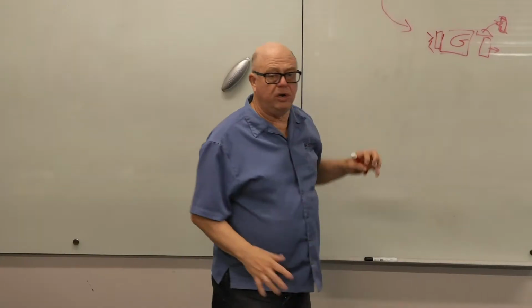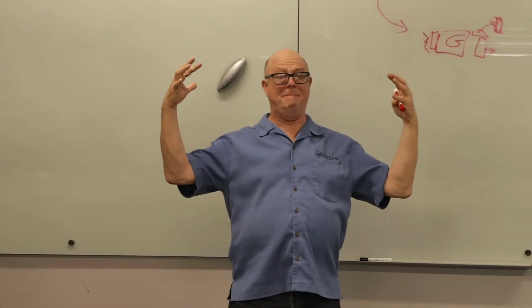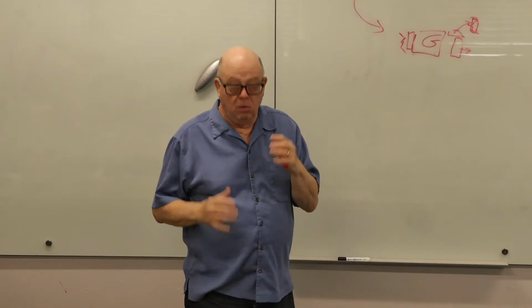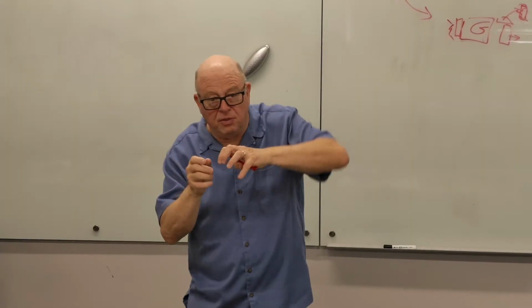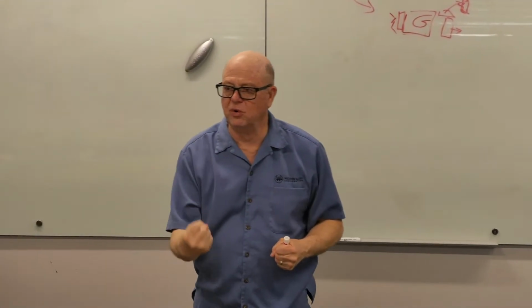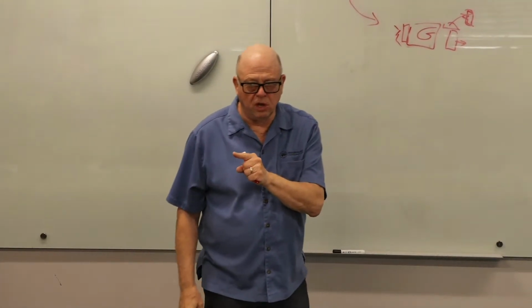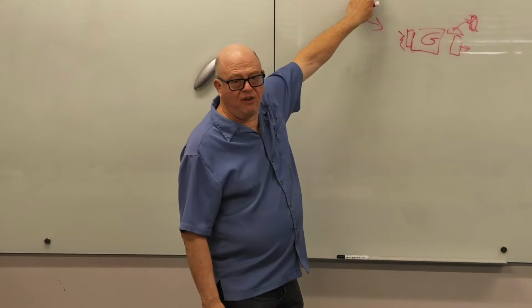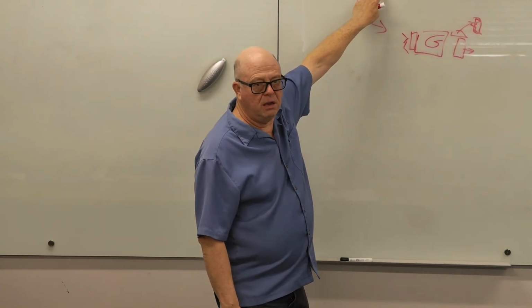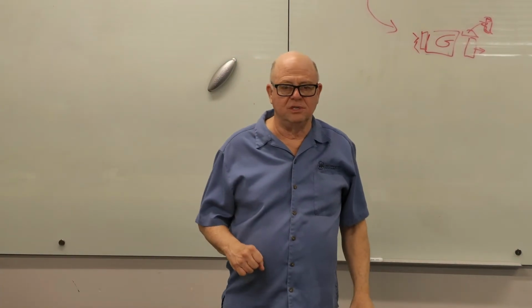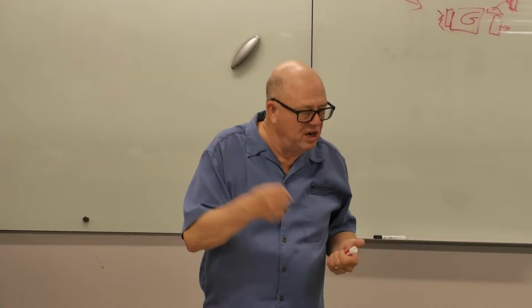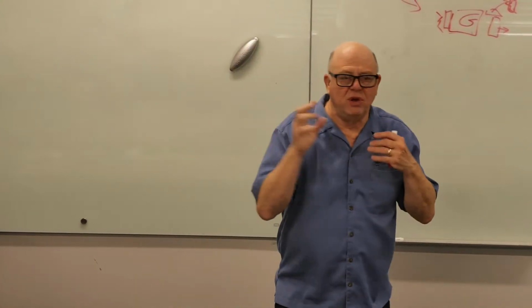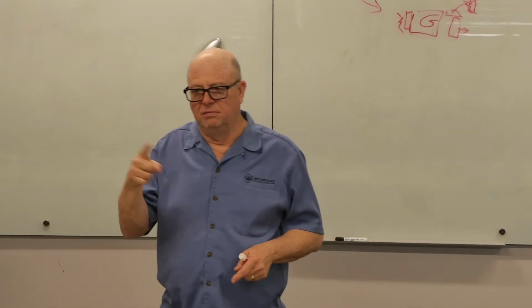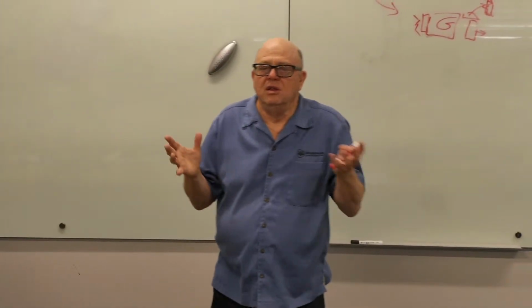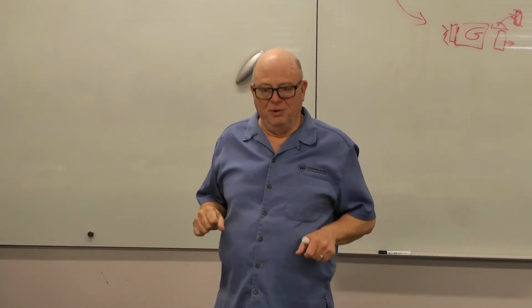In the old days, with a three-phase motor, this could be spinning backwards. We turn it on, and unless that fan wheel was just massive with lots of mass, the three-phase motor would be able to stop it and then start it turning the right direction. It had that kind of starting torque. ECM motors don't. As a result, if this gets shut off and then it's turned back on, it will continue to spin backwards, because that's what motors do if they can't overcome. Single-phase motors are famous for this. If you can't overcome the inertia, then you speed on up and you're running backwards.